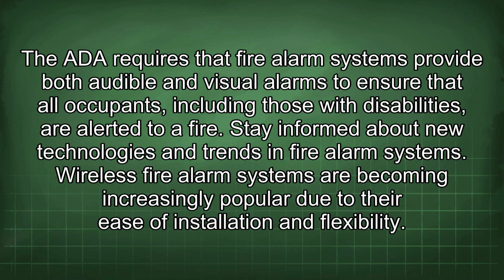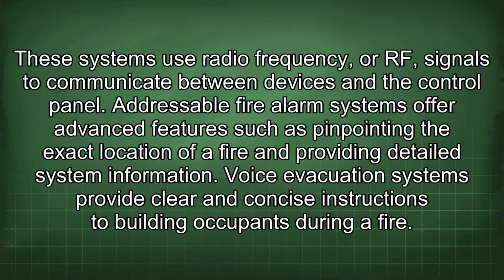Stay informed about new technologies and trends in fire alarm systems. Wireless fire alarm systems are becoming increasingly popular due to their ease of installation and flexibility. These systems use radio frequency, or RF, signals to communicate between devices and the control panel. Addressable fire alarm systems offer advanced features such as pinpointing the exact location of a fire and providing detailed system information. Voice evacuation systems provide clear and concise instructions to building occupants during a fire.